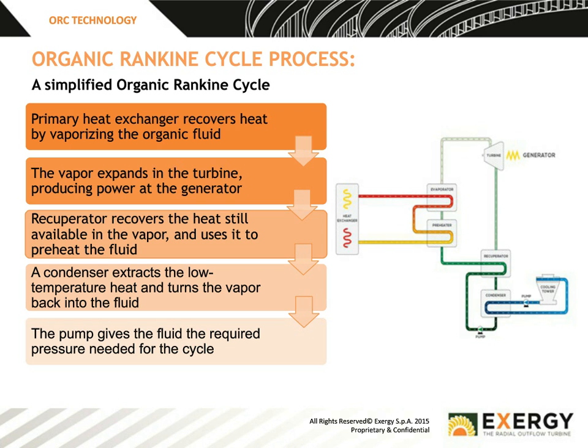This is basically the waste heat recovery system from either the engine or the industrial process. So if you can imagine that the heat exchanger here is installed in the exhaust of the cement plant, in the exhaust of the steel plant, in the exhaust of the engine. And it is used to heat an intermediate fluid. That could either be oil, it could be water becoming steam, or it could simply be hot water. Equally, in a refinery process, this could actually be the stream itself.